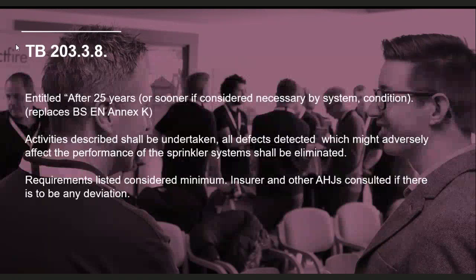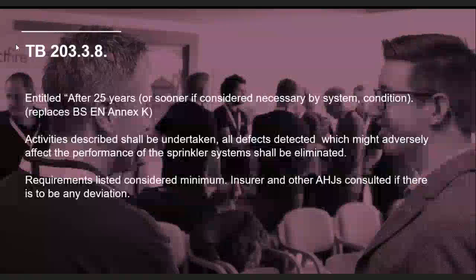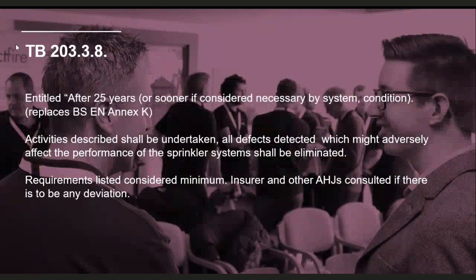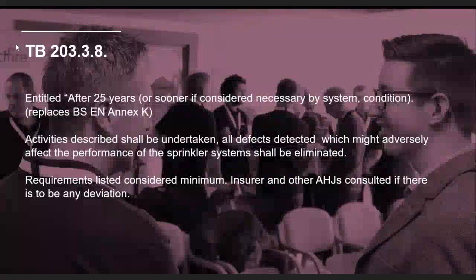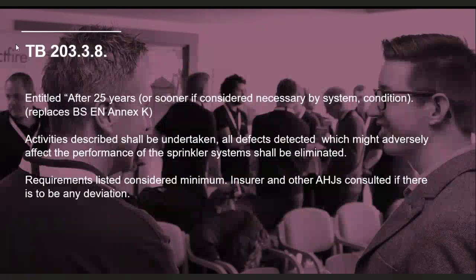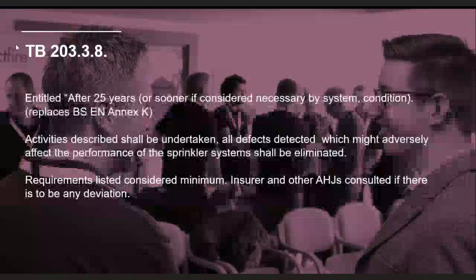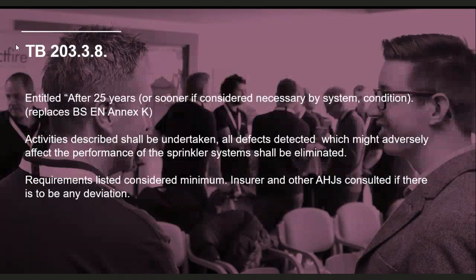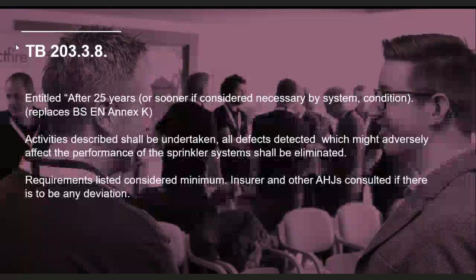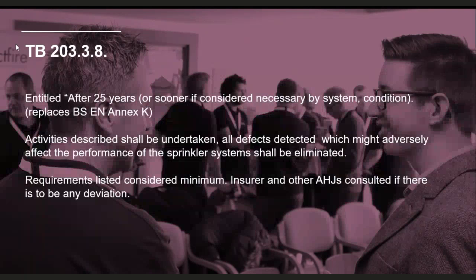So for example, sprinkler pipework works best when it's shiny and new - nice and smooth, with smaller frictional losses. As the pipes get older, the pipe is going to corrode and get rougher, which slows the water down. So does this statement mean all pipework has to be replaced to make it shiny and new again? No, I would say it doesn't. But that's where we've got this kind of catch-all statement, which may not be suitable in all cases.